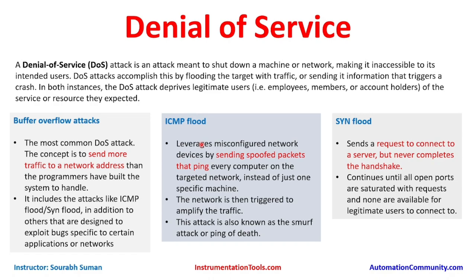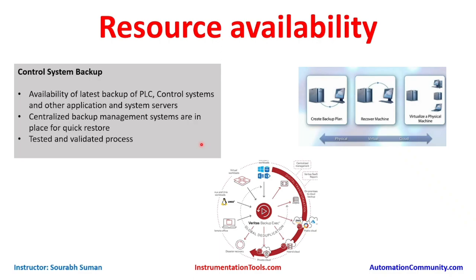Control system backup is also a type of resource availability. We need to keep the latest backup of PLC control systems and other applications on system servers so we can restore within the recovery time objective set by the organization. Centralized backup management systems should be in place for quick restore, and the process as well as the data should be tested and validated. Solutions available include Veritas, Acronis, proprietary solutions from vendors like Siemens, and Version Dog for automation and application servers.